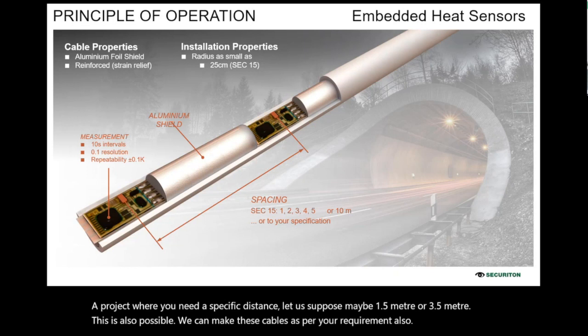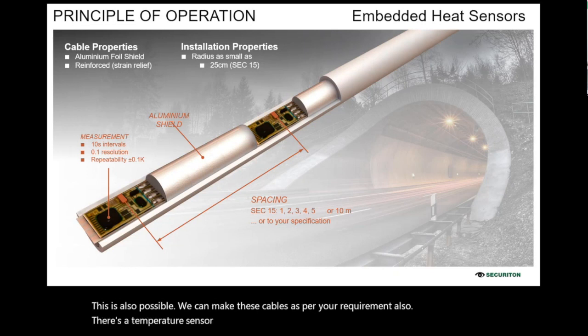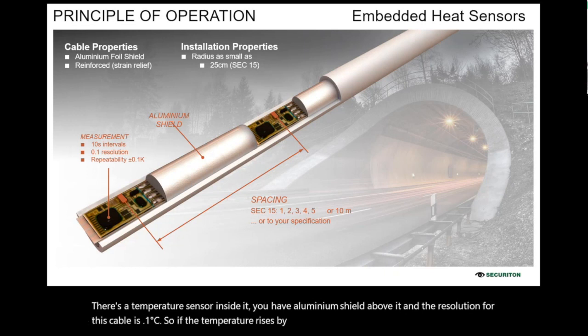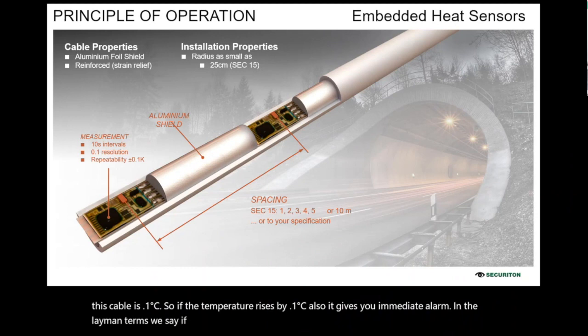There is a temperature sensor inside it. You have an aluminum shield above it, and the resolution for this cable is 0.1 degree centigrade. So if the temperature rises by 0.1 degree centigrade, it gives you an immediate alarm. In layman's terms, we say if you touch the cable, if you hold the cable, sometimes it gives you an alarm immediately.